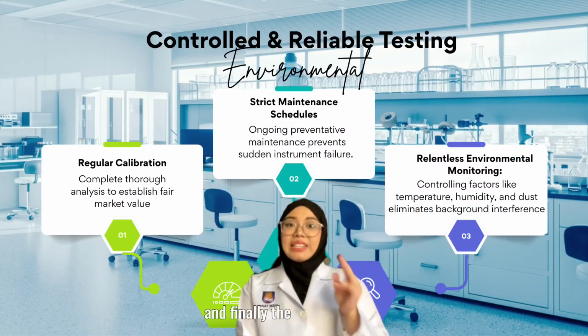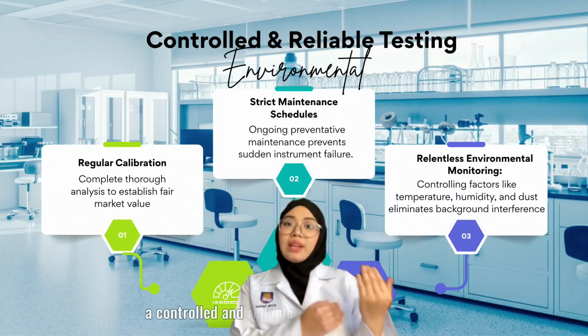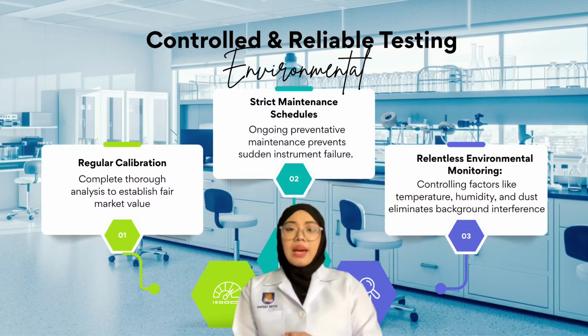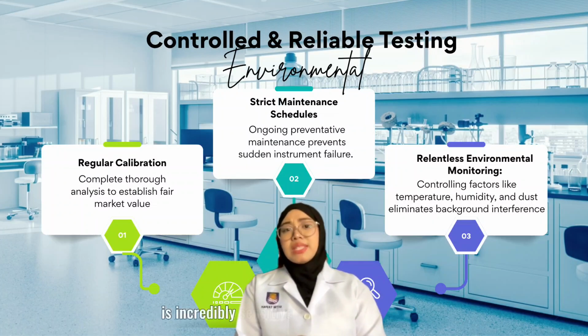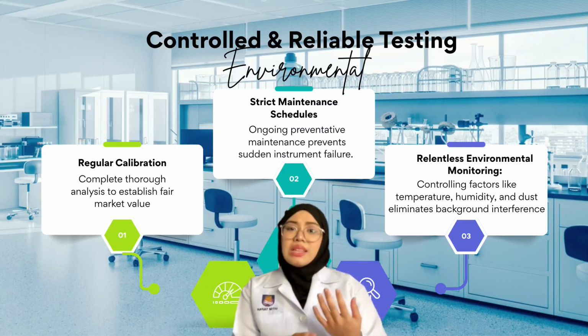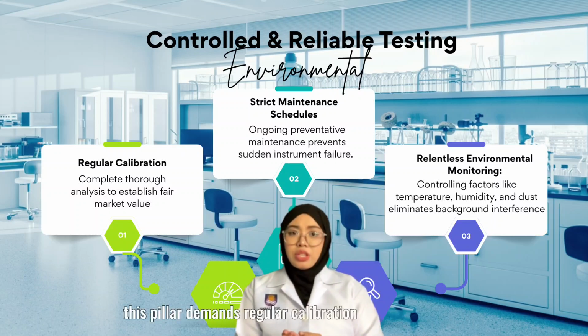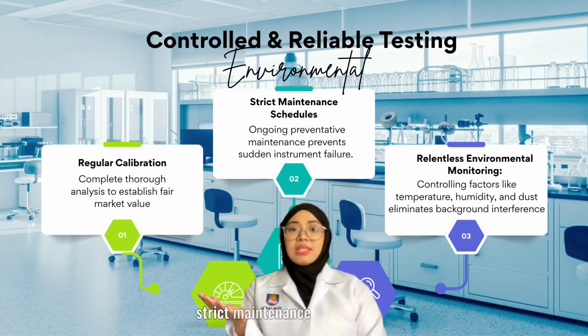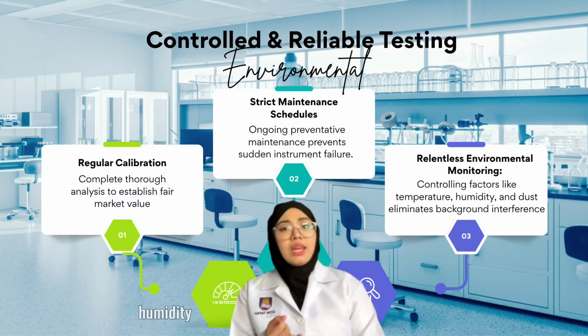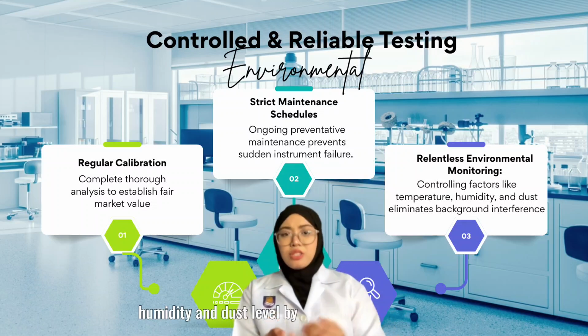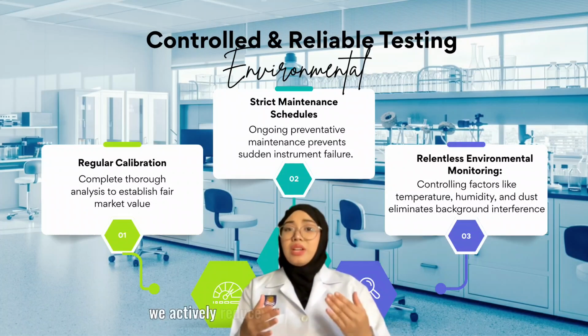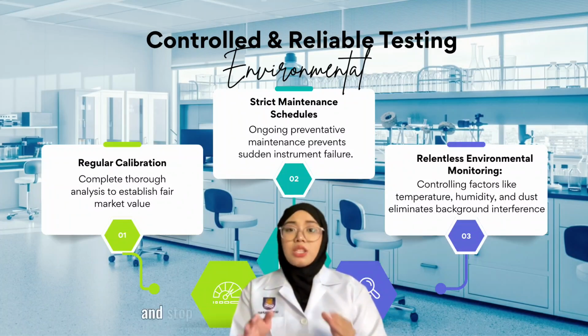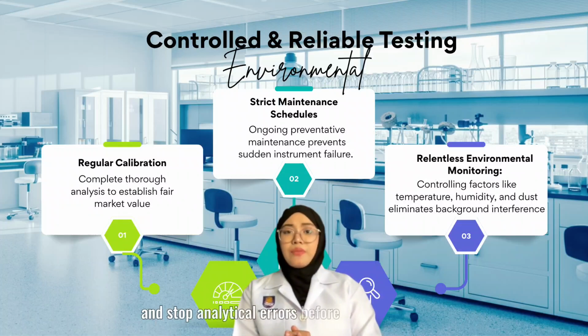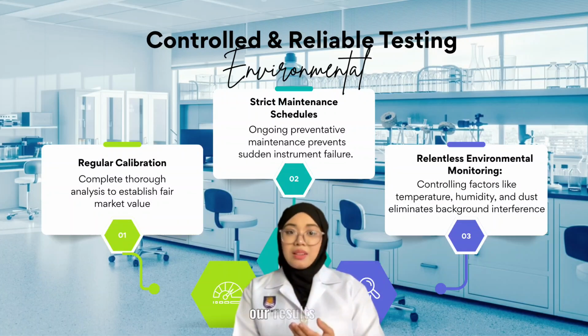And finally, the third pillar, a controlled and reliable testing environment. Analytical science is incredibly sensitive to external factors. This pillar demands regular calibration of equipment, strict maintenance schedules, and relentless environmental monitoring, like controlling temperature, humidity, and dust level. By controlling the room, we actively reduce background interference and stop analytical errors before they can ruin our results.